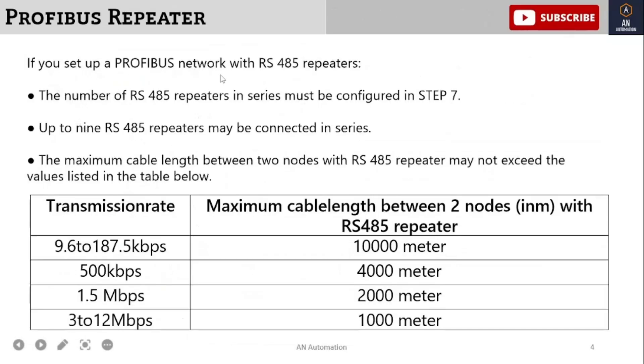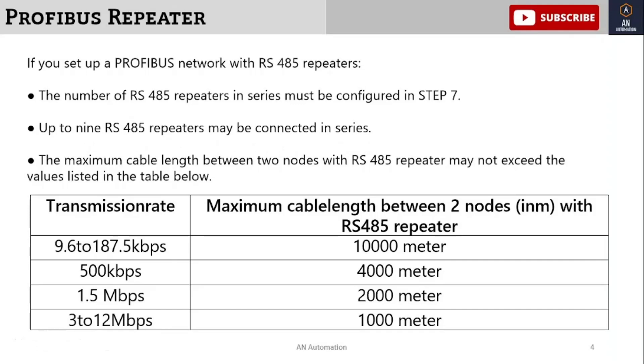If you set up a Profibus network with RS485, the number of RS485 repeaters in series must be configured in Step 7. In a series connection, all VFD drives and controllers must be configured with Step 7 using GSD files or built-in modules. Up to 9 RS485 repeaters can be connected in series.